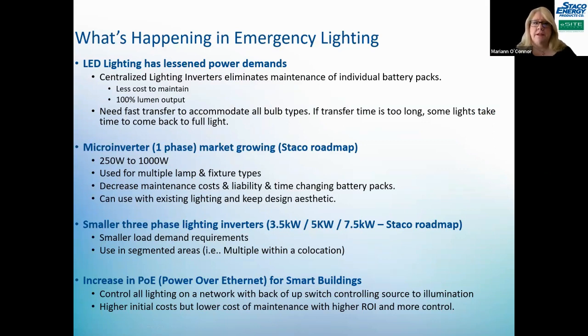We are definitely seeing lesser demands for lower loads. With LEDs, the power requirements are declining, so the kVA or kW rating of the lighting inverters is definitely going down. About 3-4 years ago, I was seeing a lot of 15 kW single phase lighting inverters. Now I'm hard pressed to see something that high — they're falling in the under 10 kW range, and I'm seeing a lot in that 5 kW and less range. When you have a centralized lighting inverter, which is what Staco has, it's less to maintain when you have that centralized lighting inverter.